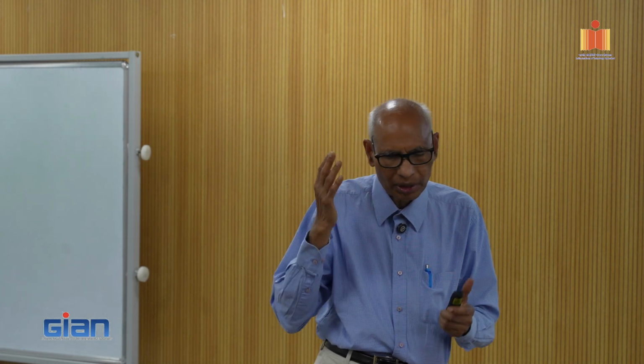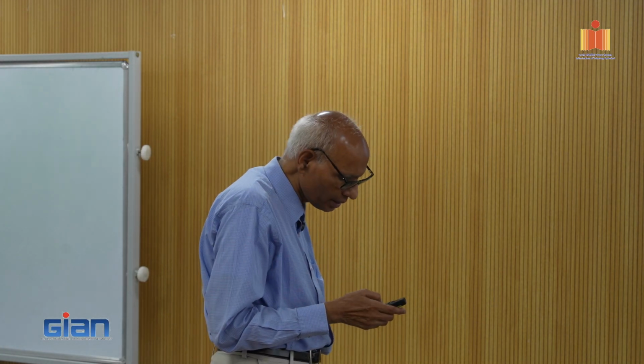Penumbra trimming, penumbra trimmer. That kind of penumbra trimmer concept has been there since cobalt-60, because cobalt-60, because of its source size, used to have a very large penumbra. So in order to reduce the penumbra, you put a penumbra trimmer, some kind of a collimator, okay? So the Mevion beam has a dynamic collimation. They claim that by that way, they can make a very high dose gradient for lateral OAR sparing. Okay, so you saw the scanning beam nozzle now. This is a Hitachi system. Other beams have similar things, okay?